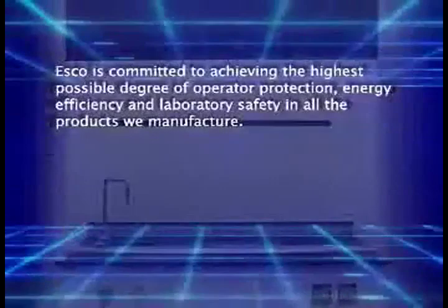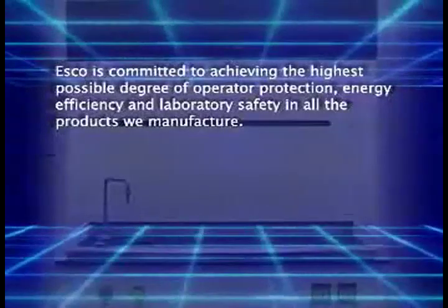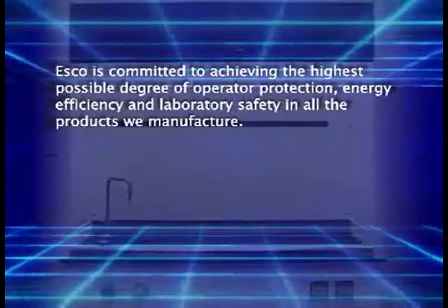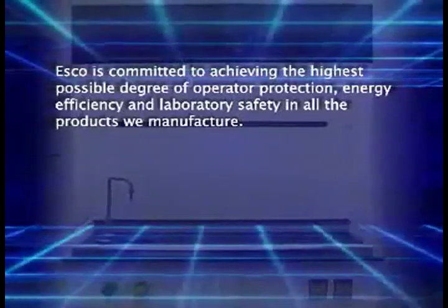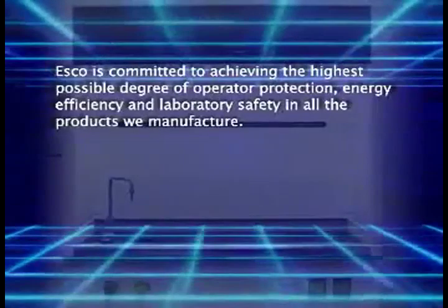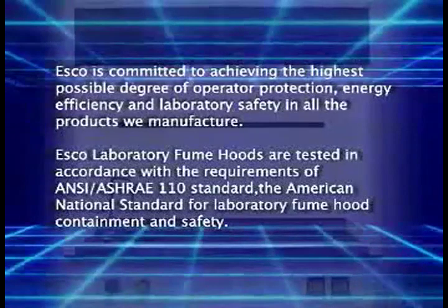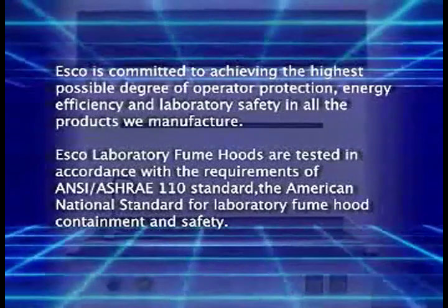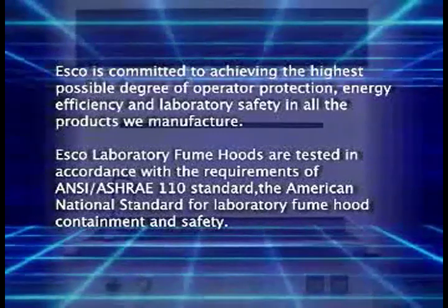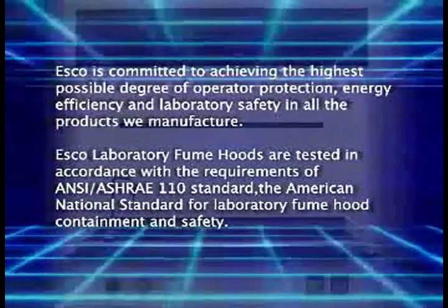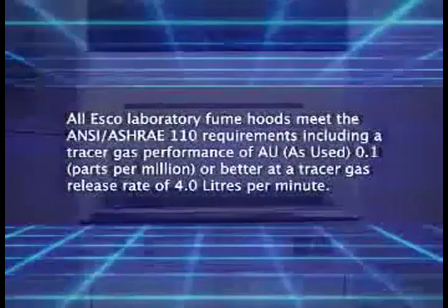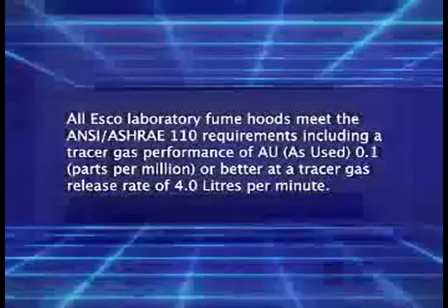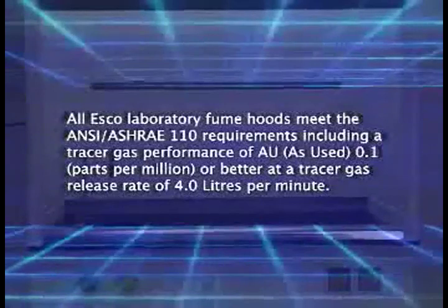At ESCO, we are committed to achieving the highest possible degree of operator protection, energy efficiency, and laboratory safety in all the products we manufacture. Our laboratory fume hoods are tested in accordance with the American National Standard for Laboratory Fume Hood Containment and Safety. Every laboratory fume hood we manufacture meets or exceeds the requirements of the ANSI ASHRAE 110 Standard.